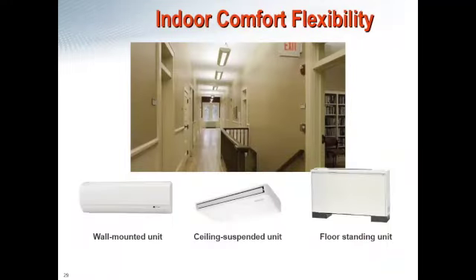So now, moving right along, we're going to pass a lot of the application side of things, and I'm just going to touch on, for the end of the presentation, a lot of the different kinds of indoor units that most VRF manufacturers have to offer. The first and most common unit that you're going to see is the wall-mounted unit. I know probably the most common application of VRF in America right now is the wall-mounted unit. That also goes for worldwide. While we really do know it is not the most aesthetically pleasing unit, it is by far the quietest and most efficient. So if you're dealing with an application where the owner is okay with the wall-mounted unit, the installation flexibility is great, and the efficiency is really off the charts.